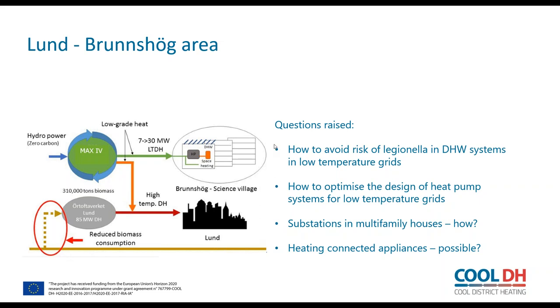So when you make such a system with low temperature, you have some technical questions. One is how to avoid legionella in your hot domestic water system when you have low temperature grids. Another question is when you utilize combination of cooling machines and heat pump, what is the optimal design of those configuration at the supply side? When you go to the multi-family houses, you can ask yourself, what is the optimal solution for the substations? And also think about, would it be possible to connect appliances directly to the supplied district heating?